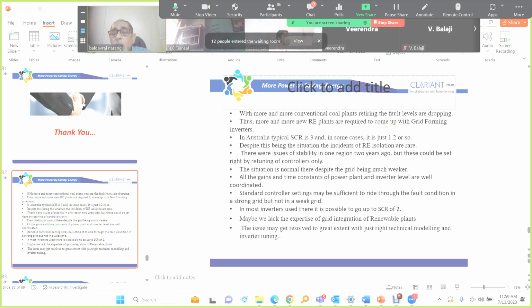And what happens is during fault conditions these PPCs freeze -- they are not available for any control. PPCs are only for steady state control. Absolutely, during fault conditions inverters are left on their own. They have to manage with their individual default controls only, at their own LT output. They cannot manage at the point of interconnection unless there is closed loop communication. Yes, that closed loop has to be there.